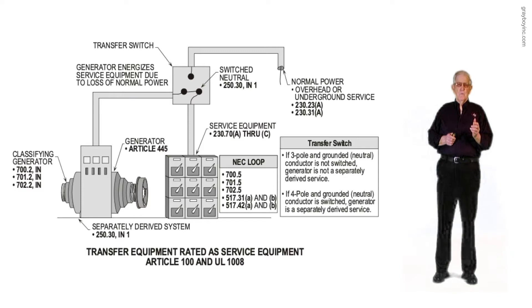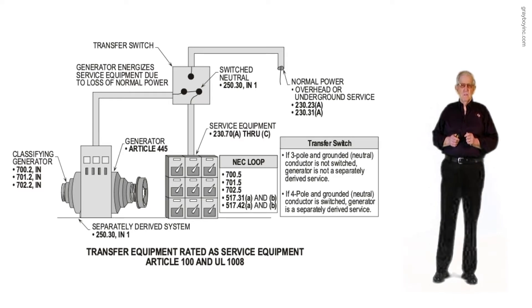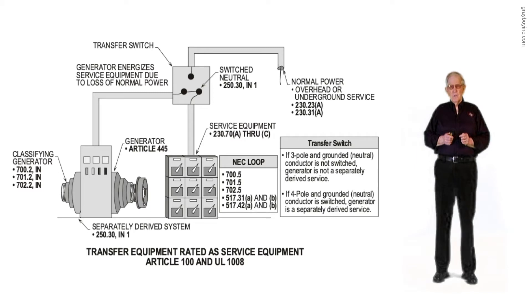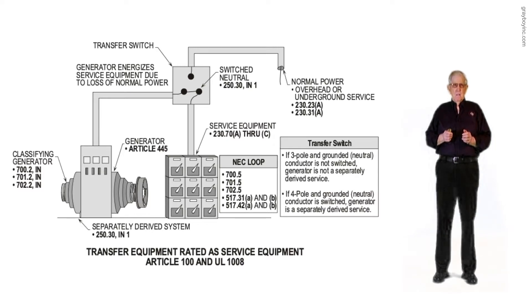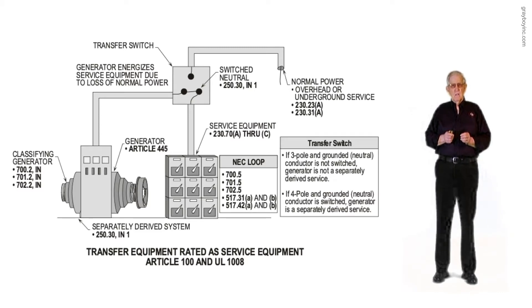The rules are found in Article 445. Reviewing the generator classification shown at the left in the illustration: an emergency generator, in accordance with 700.2 informational note, supplies certain loads for the generator to be classified as an emergency generator. 701.2 informational note lists the loads a generator supplies to be classified a legally required standby generator. 702.2 informational note lists the loads that an optional standby generator would supply.